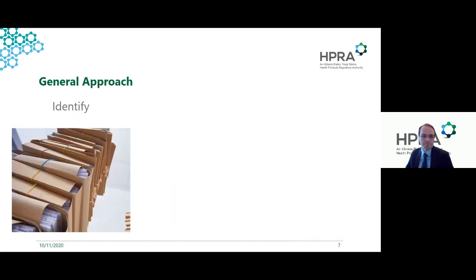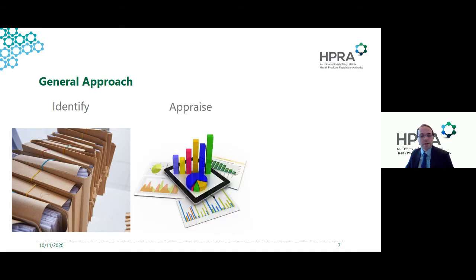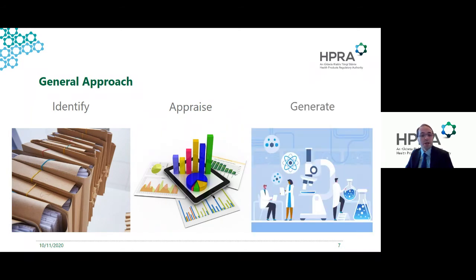So as a general approach, when you're considering looking at scientific validity, analytical performance, or clinical performance, the first thing you should do is identify the information that you have available to you now. What data do you have under each of these three headings? Then assess or appraise the data, and determine: is this sufficient to support the use of the device? And if not, is there a need to generate additional data, or a need to look at other sources of data to support the use of the device?